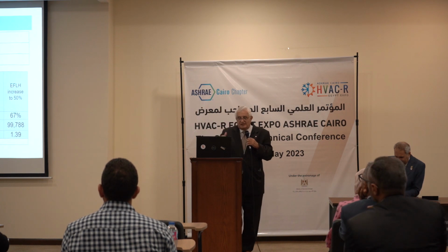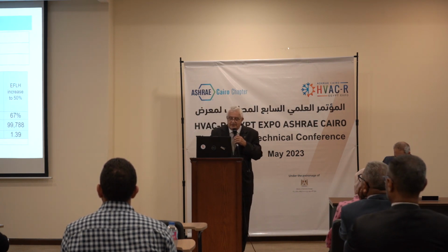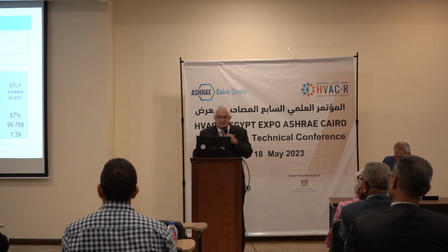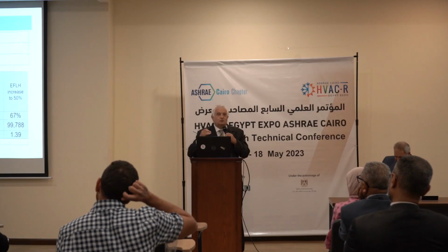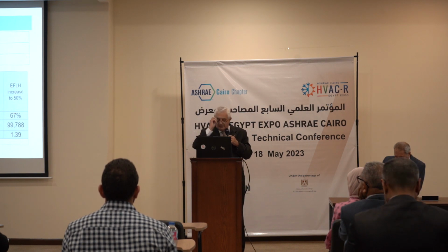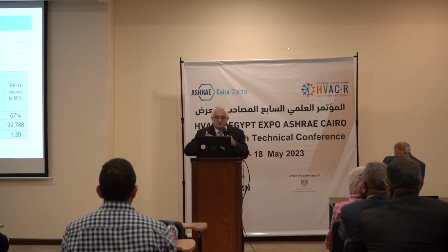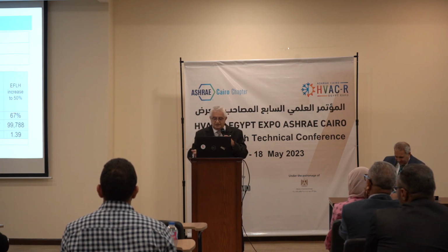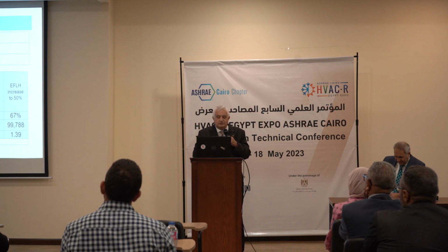But if you increase the EFLH to 40%, then the payback is 1.85 years, fast. And the IRR is 51%, very high. And if you increase it to 50%, if the machine is working 50% of the year at its full capacity, then the NPV is about 100,000 pounds and the payback is only 1 year 39. So in other words, even with 26% EFLH, the machine works. When you go down to 16%, then it's not really worth it. But anything over 25% EFLH, the very important EFLH, it's an advantageous system.